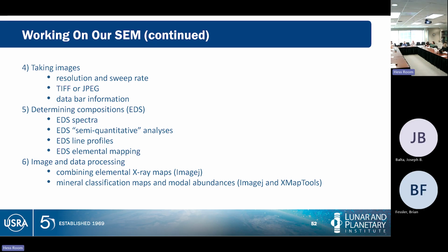And also, how long do we collect image data at any single point? Do we collect a high pixel image where we move across, or do we collect a more broad image? Those are things we can select and change. We then move to the spot we want to go to on our sample.